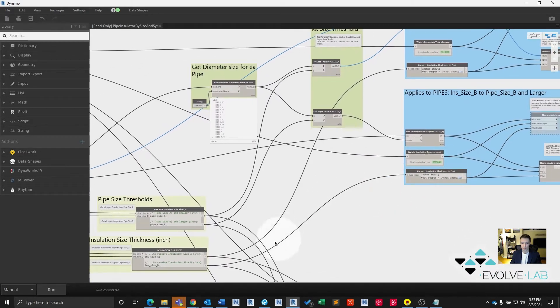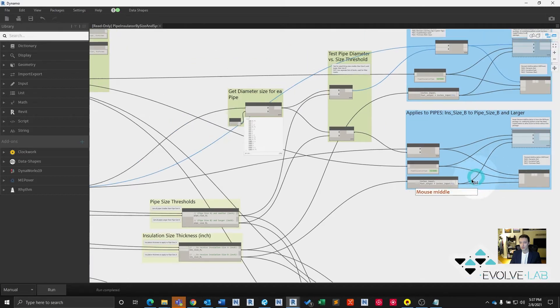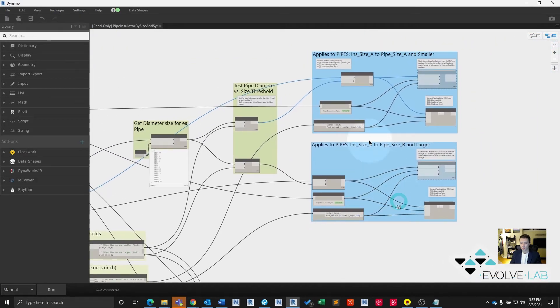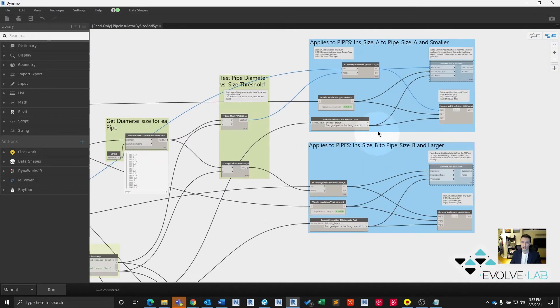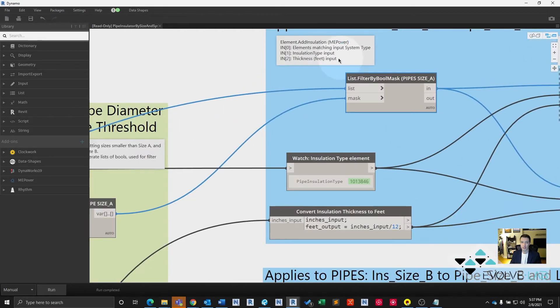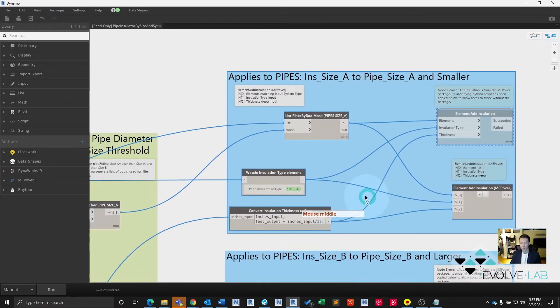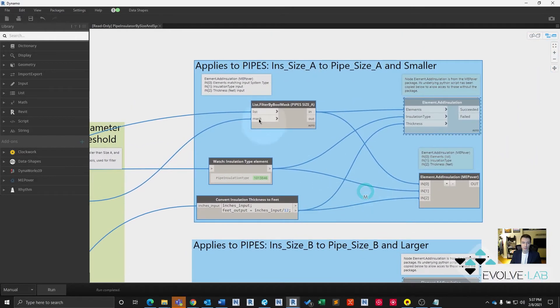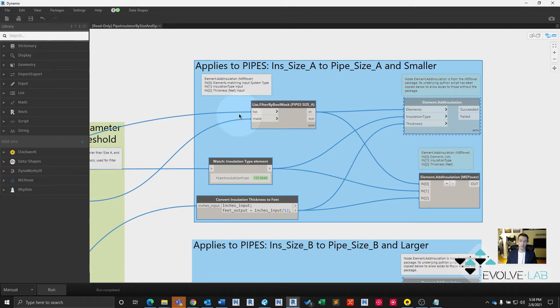You can see that if you follow the spaghetti mess here, they each go to the different insulation sizes. Finally, now that we have our input system type, the insulation type, and the thickness, which has been converted to feet here, we can use those and the MEPover package node Element.AddInsulation to actually add insulation to our Revit elements.